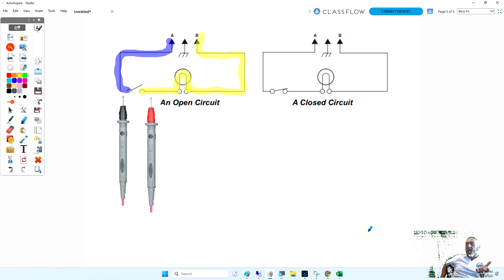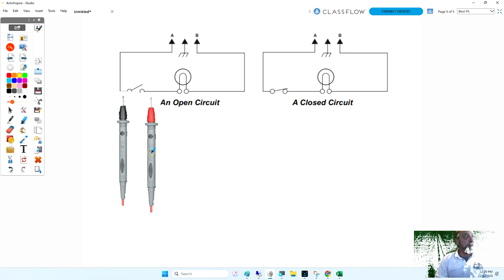I tell my students I don't like checking voltage across a switch. It gets confusing, especially if you're on the wrong switch. I'd rather you, when troubleshooting, have one meter lead here and one here, and backtrack through the circuit to find voltage. If I went all the way to point A and got no reading, I'd put the black meter lead back on the bulb and go to the other side of the circuit finding voltage. That's what we do when troubleshooting.